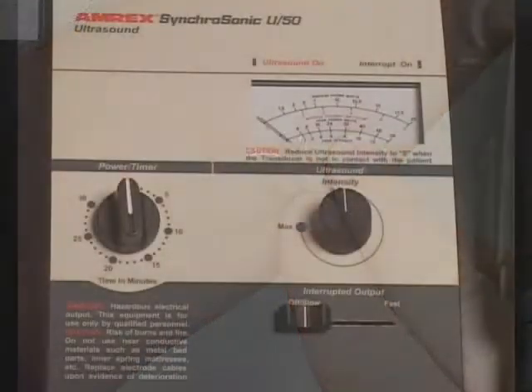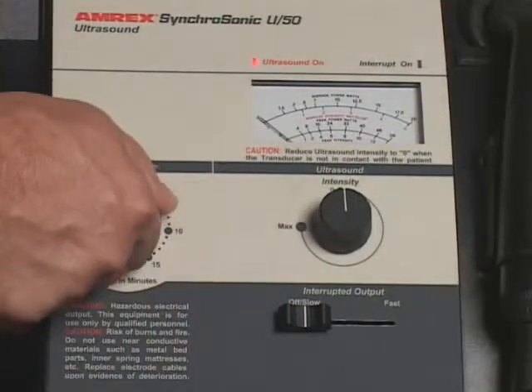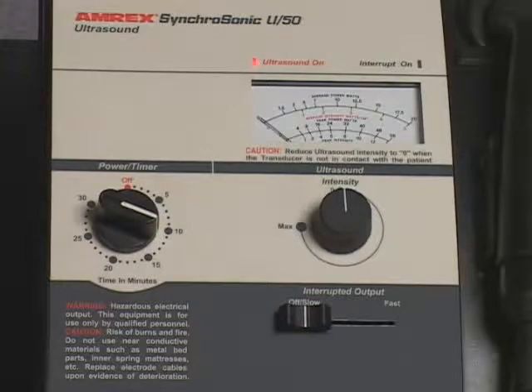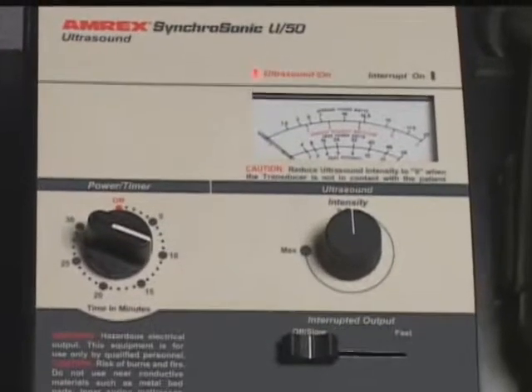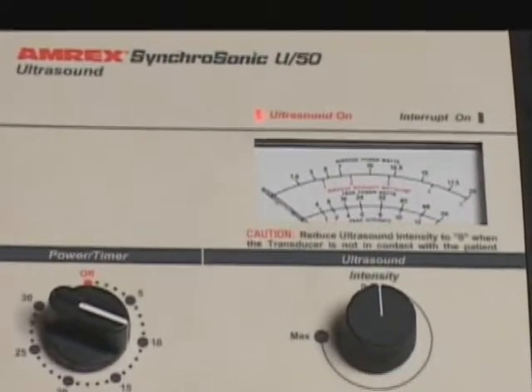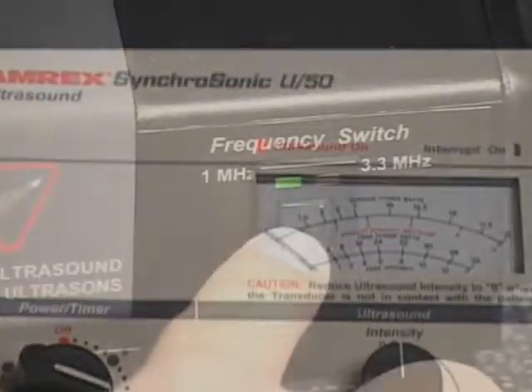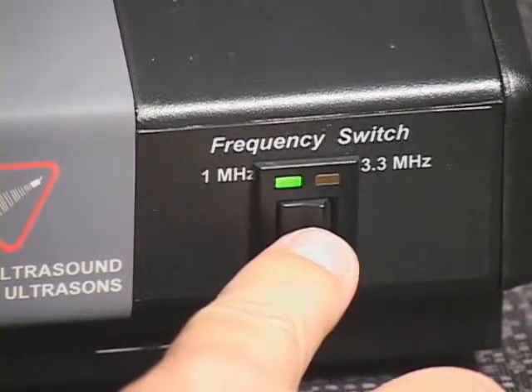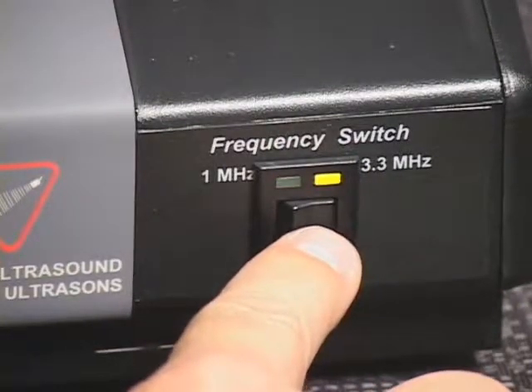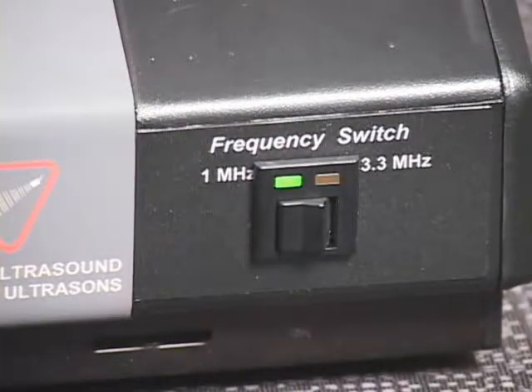Prepare a contact medium at and around the treatment site with a liberal coating of Amrex conductance and coupling gel. Rotate the power timer knob and set it to the desired treatment duration. The ultrasound on indicator light, located above the upper left corner of the ultrasound meter, will illuminate. If the ultrasound generator is equipped with the 1 or 3.3 MHz output frequency option, set the ultrasound frequency switch to the desired ultrasound output frequency.